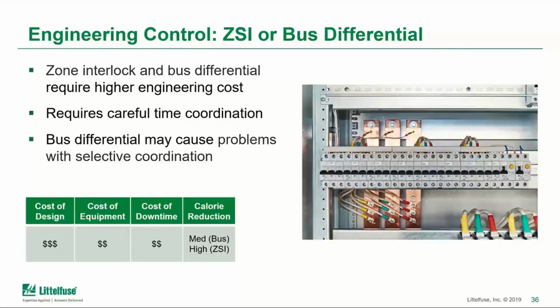Here we've listed the cost of design a little bit on the higher side because of the engineering requirements we're talking about to select the breaker settings and do that coordination in advance. The cost of the equipment itself is pegged at the medium level, as we're talking about potentially retrofitting a number of breakers and adding current transformers if we're in a retrofit application.